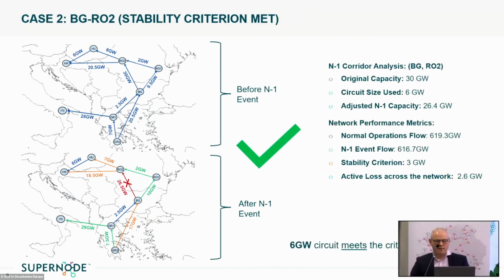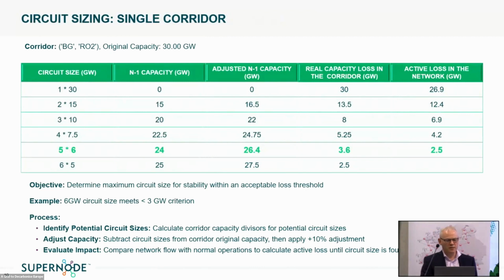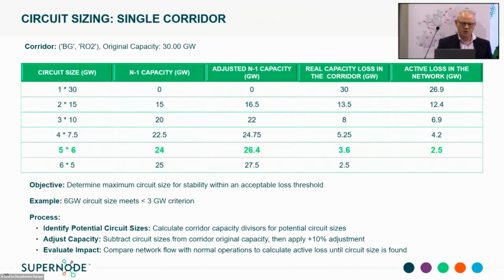When we get to 6 gigawatts, when we lose 6 gigawatts, you can see the X, it's hit here. Between Bulgaria and Romania 2, we lose 6 gigawatts, but the other circuits have overload capacity of 10%, so they pick it up. The outcome is 2.6 gigawatts of loss, so that's acceptable, it meets the criterion, which is an input to the model. We do this across all the circuits, but for this particular hour, we go down to 6 gigawatts and it's satisfactory - obviously 30 gigawatts is too big.